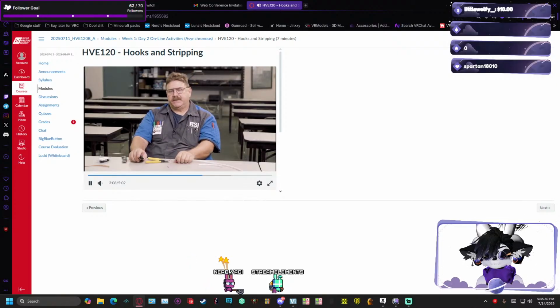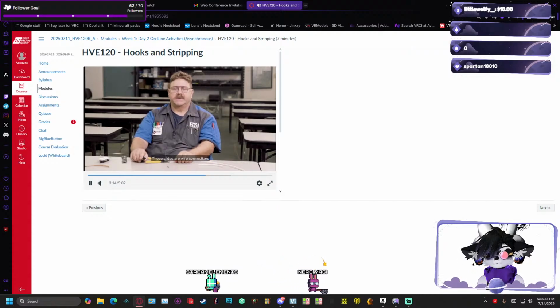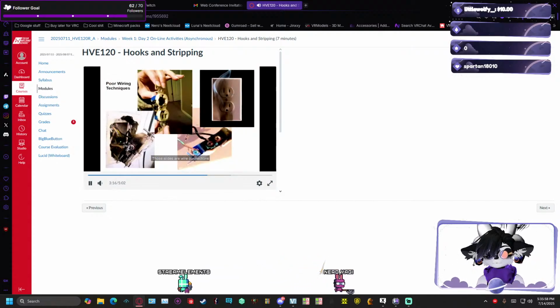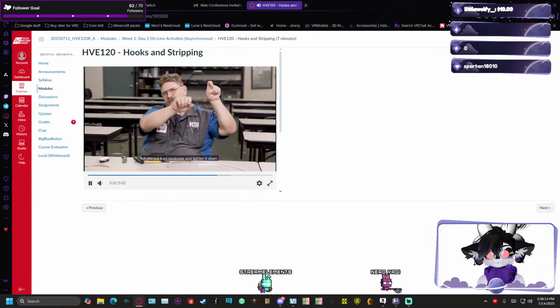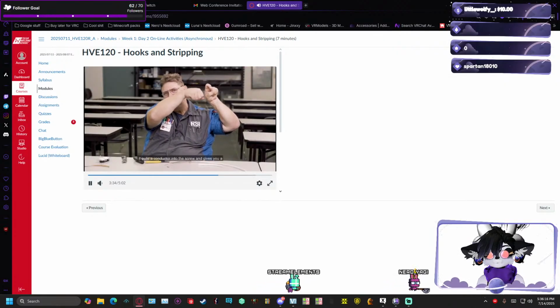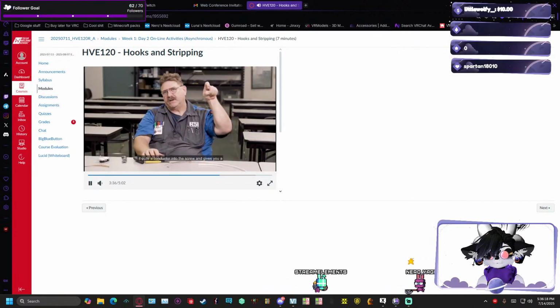If you happen to get bad connections, on the slide you'll see some of the results. Those slides are wire connections that were either improperly made or not put on the screw in a clockwise direction. Remember, clockwise, right tight, left loose. If you put it onto the left and tighten the screw down, it's going to try and straighten that wire out instead of pulling it into it. If you put it on clockwise and tighten it down, it pulls the conductor into the screw and gives you a better connection.